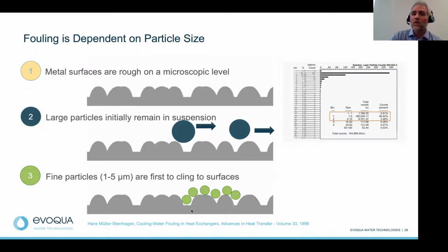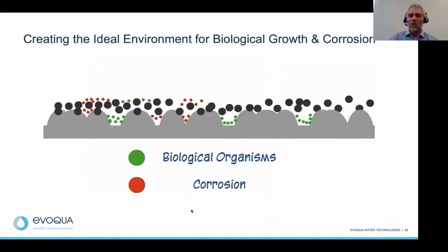So when we talk about cooling water having such fine size particles, what does that do, right? This is really where you have the first layer of biofilm or biological growth that starts to accumulate and deposit on your heat transfer surfaces. That biological growth starts to potentially create a layer for under-deposit corrosion and creates a host of difficulties for your chemical program. So if you can eliminate those fine particles from your cooling water, you're setting yourself up for a lot better success for controlling solids, but also for the overall health of your water treatment program.